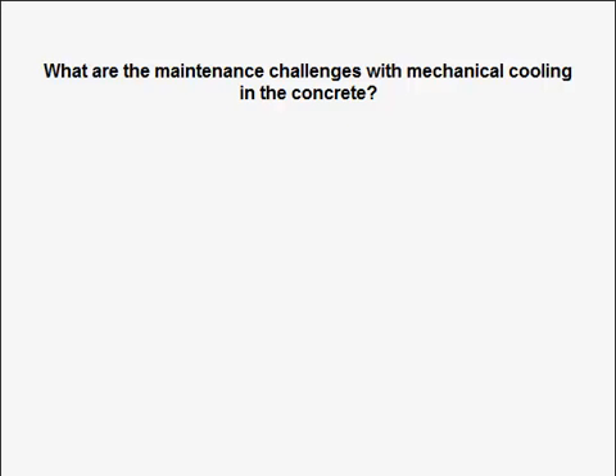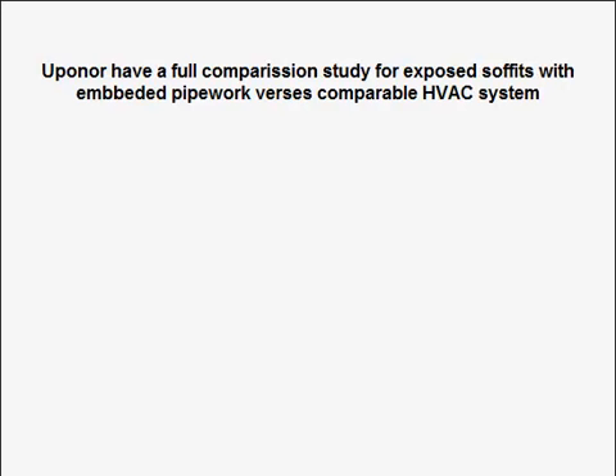Not that I'm aware of. There may be, but I haven't come across such a study. To some extent it's comparing apples with oranges, because buildings with pipes embedded in the soffit are slightly more free running, so you'd expect the internal temperature to be allowed to vary more than in an air-conditioned building with tighter control. But in terms of CO2 emissions, I've looked at a range of passively cooled buildings with concrete floors and added up the average CO2 emissions, and it comes out at about 40 kilograms per metre squared per year, compared to around 75 to 80 kilograms per metre squared for a good practice air-conditioned office. So roughly, very roughly since it varies project to project, it's about half the CO2 emissions.